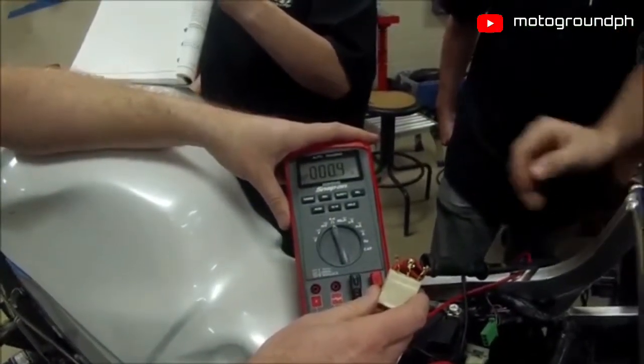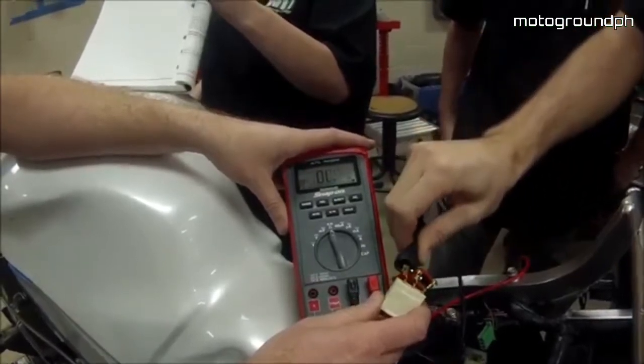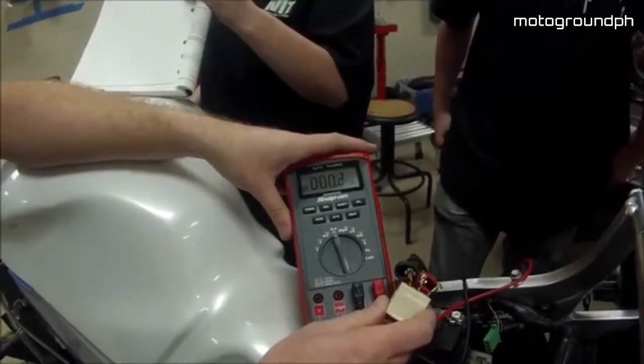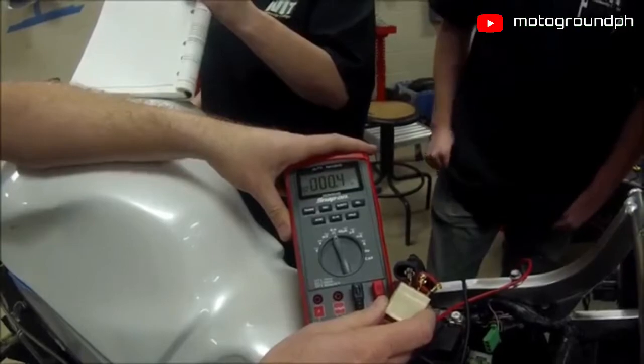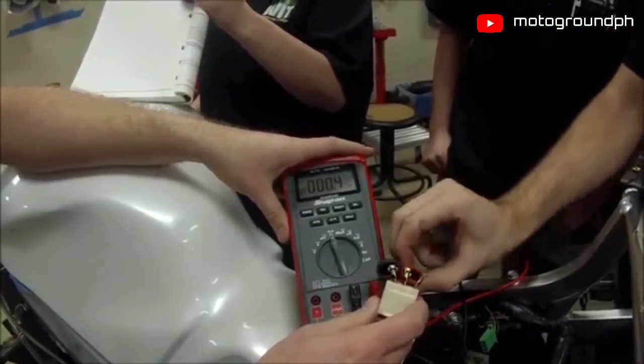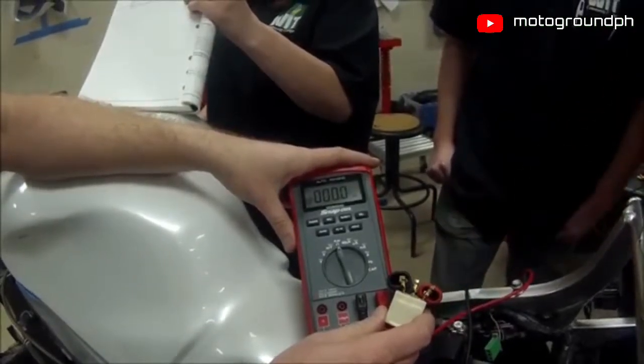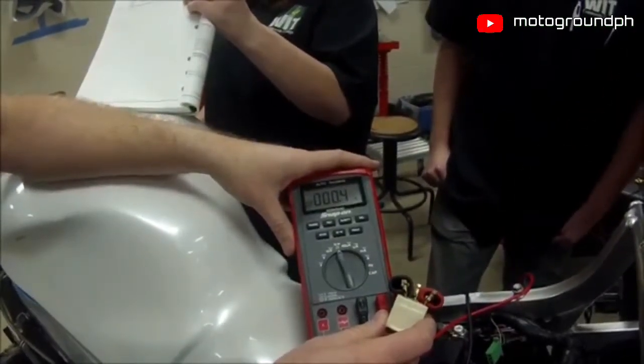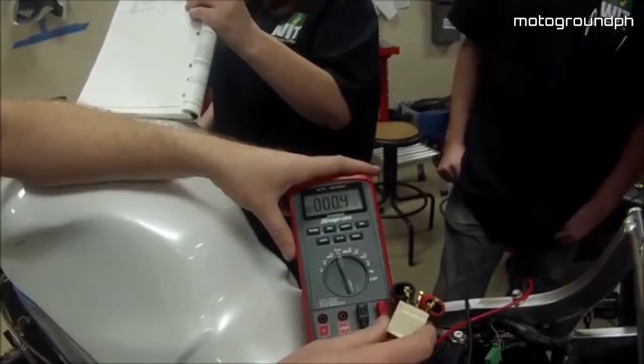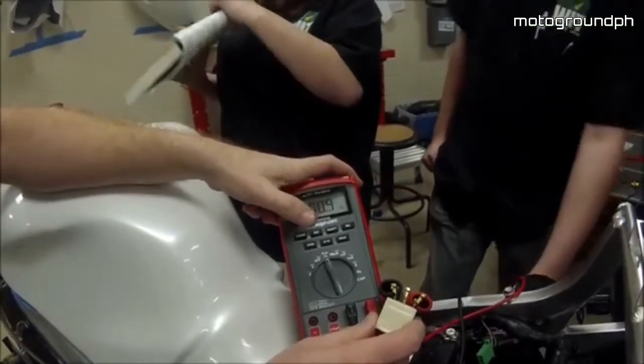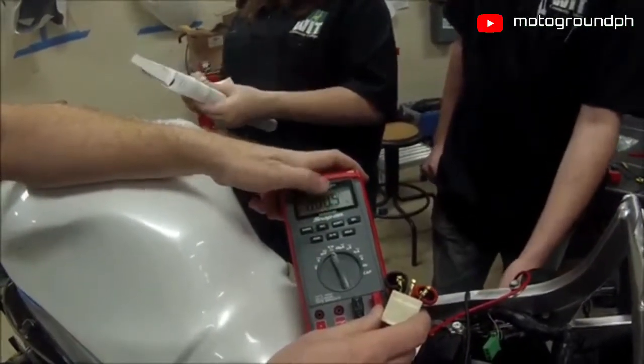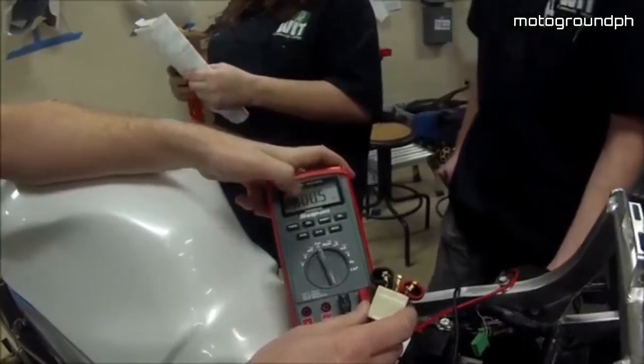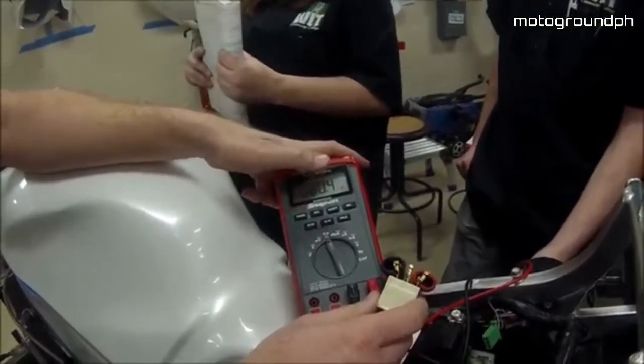0.5, that one's good, switch it. Those fuses really throw us off on those poor leads, don't they? 0.5, now switch the middle one over. So the continuity between all those is good. Even if we went to 0.6 and had 0.1 of resistance in there, we'd subtract that from those readings. So we're good, we're within our specs.